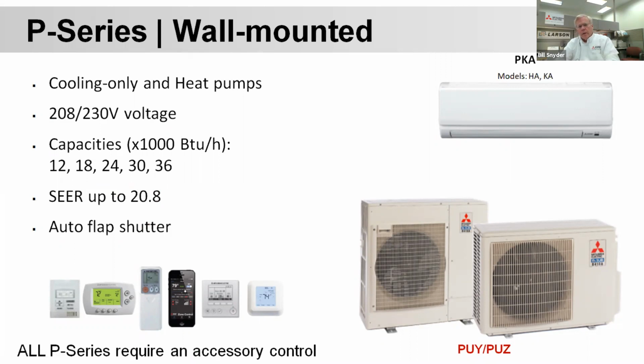Now, the P series, this is a cooling only unit. The P series is what we would use. It's a professional series, is what we would use in like a server room application. Out of the box, it's good to, I think, 0 degrees, no, 23 degrees or something like that out of the box. If you put a front wind baffle on it, it's good to 0.